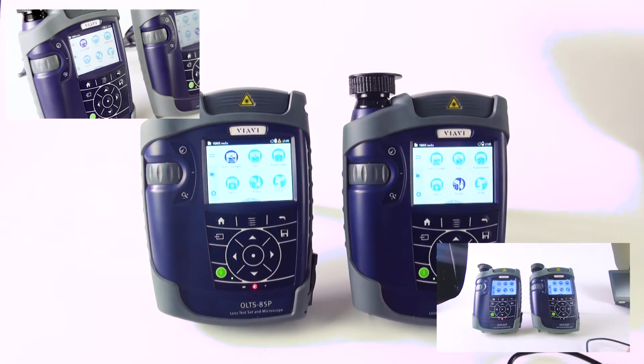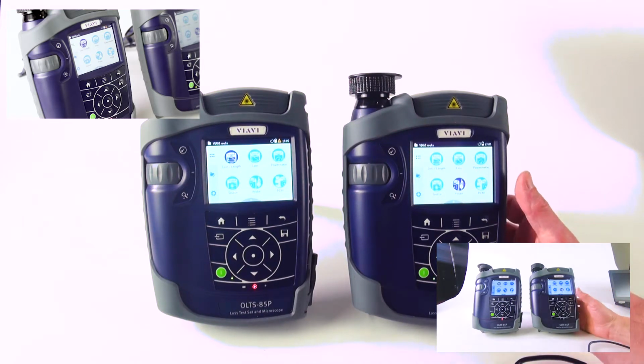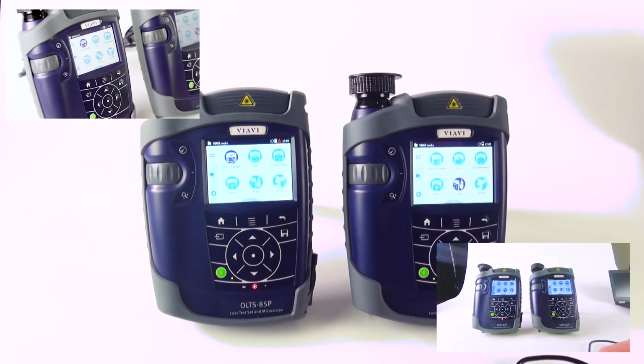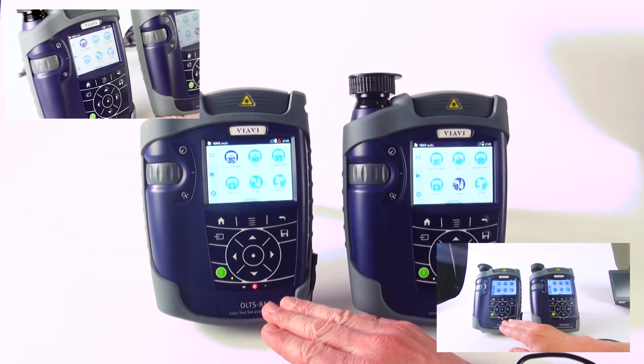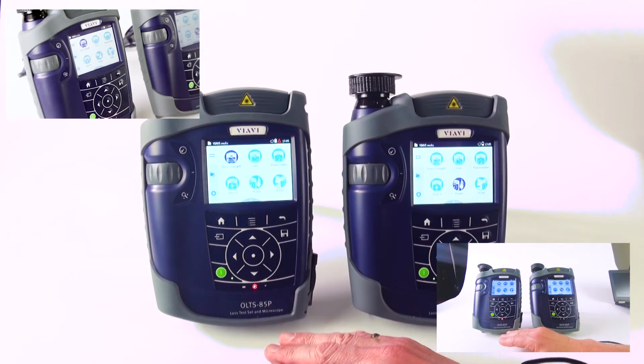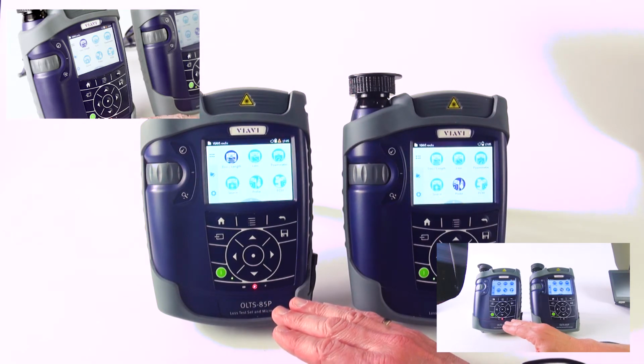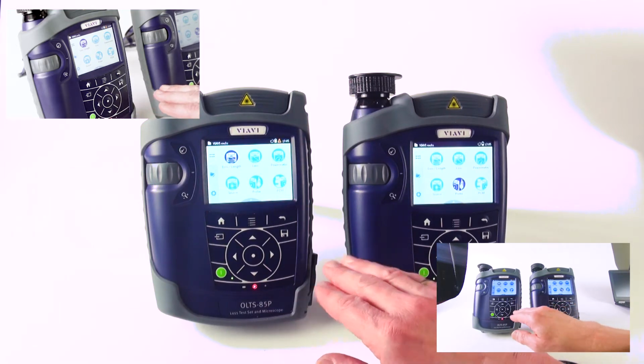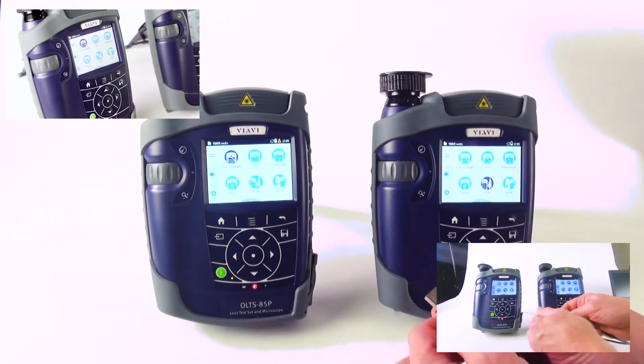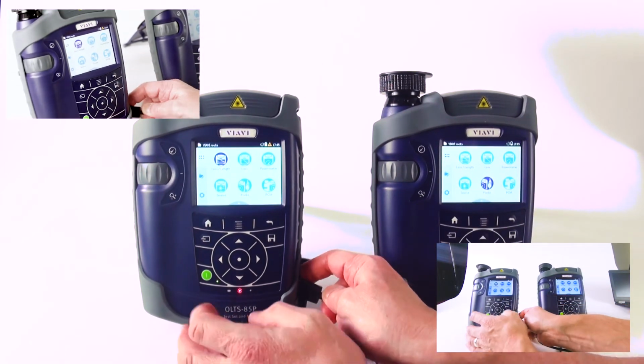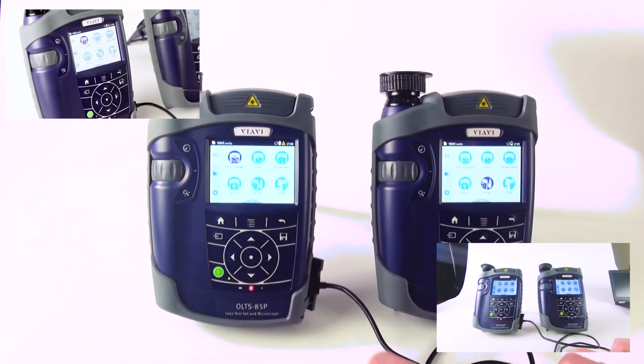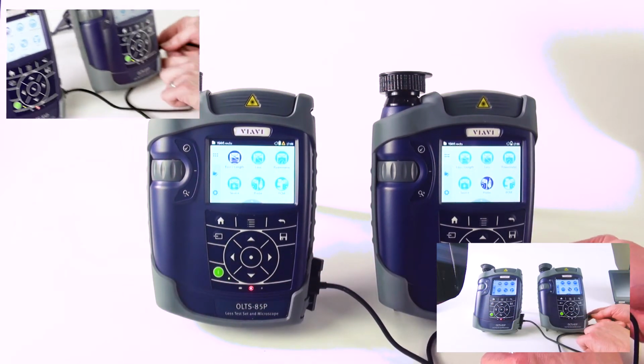What you may want to do with the OLTS in this case is that we've saved end face inspection results on both the remote unit as well as the local unit. And because all our reporting is done by the local unit, the first step that we need to take is to transfer those end face inspection results from the remote to the local. And we do that by taking the two units and connecting them by USB using the supplied USB cord.